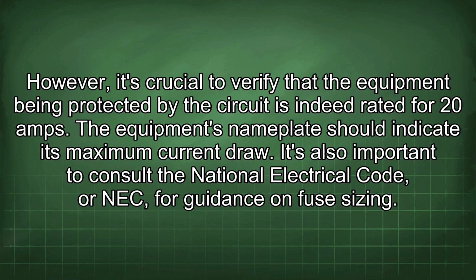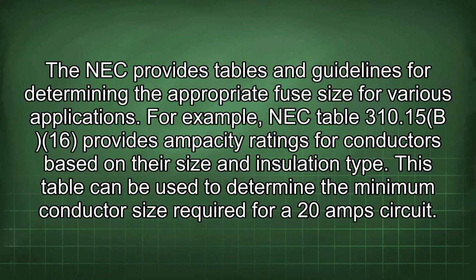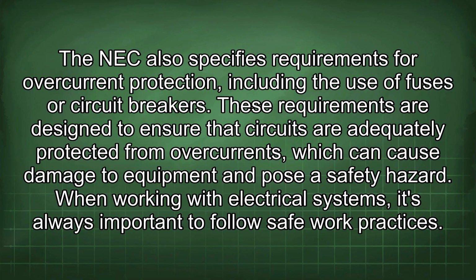However, it's crucial to verify that the equipment being protected by the circuit is indeed rated for 20 amps. The equipment's nameplate should indicate its maximum current draw. It's also important to consult the National Electrical Code, or NEC, for guidance on fuse sizing. The NEC provides tables and guidelines for determining the appropriate fuse size for various applications. For example, NEC Table 310.15(B)(16) provides ampacity ratings for conductors based on their size and insulation type. This table can be used to determine the minimum conductor size required for a 20 amp circuit. The NEC also specifies requirements for overcurrent protection, including the use of fuses or circuit breakers.